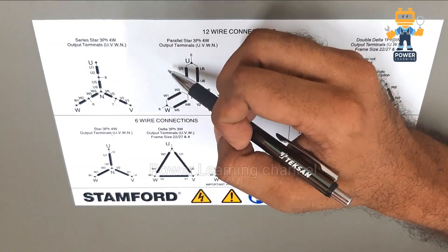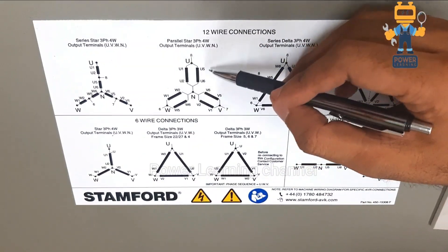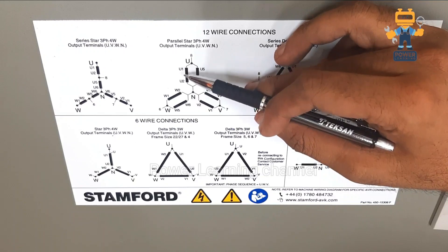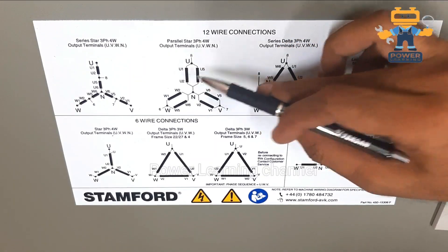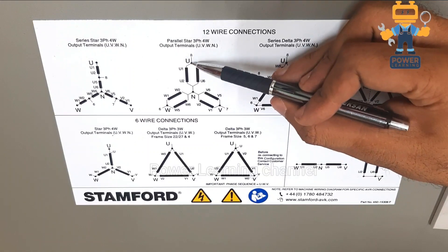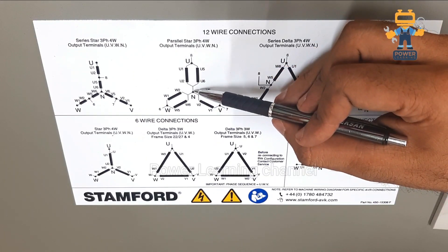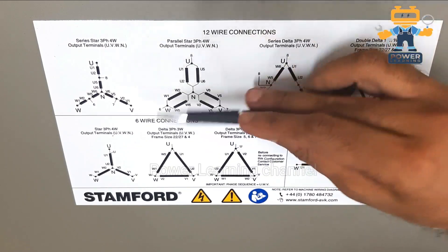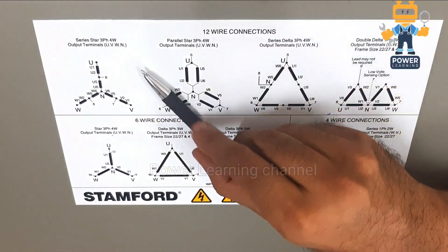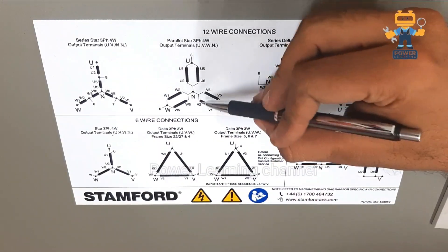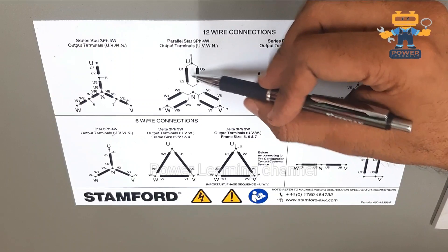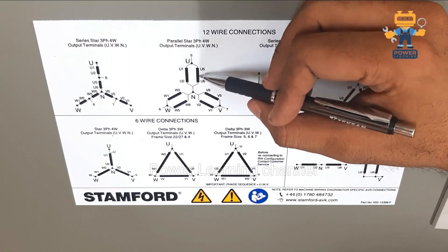In parallel star, we have one coil with two ends — u1, u2 and u5, u6 — and both coils make one phase of the generator. The two starting ends are connected together and the two other sides of the winding are connected together. All three phases have their winding ends now connected at neutral, so each phase winding is connected in parallel with each other.